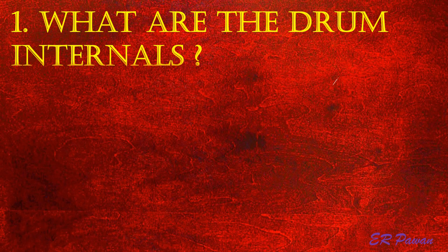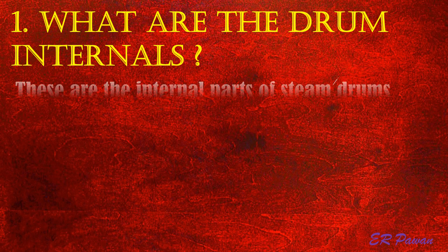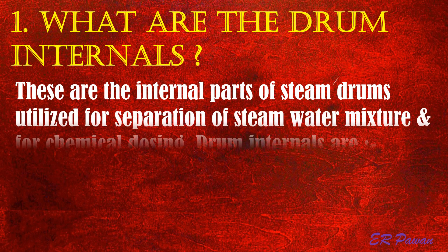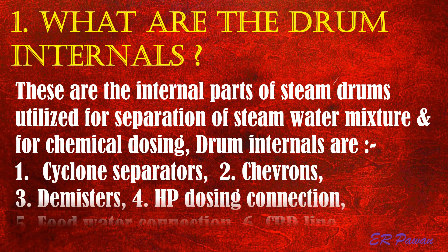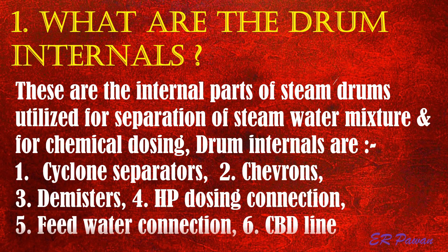Question 1: What are the drum internals? These are the internal parts of steam drums utilized for separation of steam-water mixture and for chemical dosing. Drum internals are: 1. Cyclone separators, 2. Chevrons, 3. Demisters, 4. HP dosing connection, 5. Feed water connection, 6. CBD line.